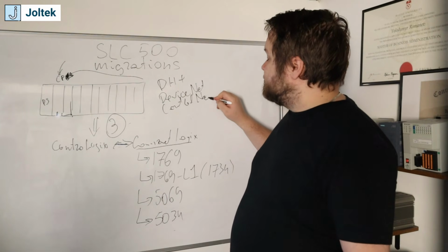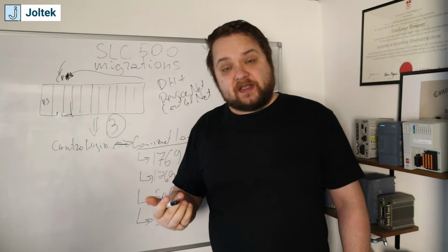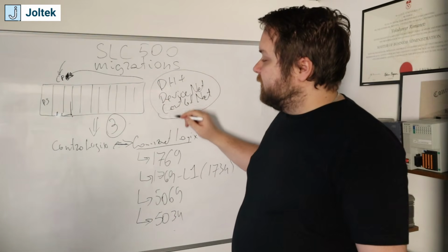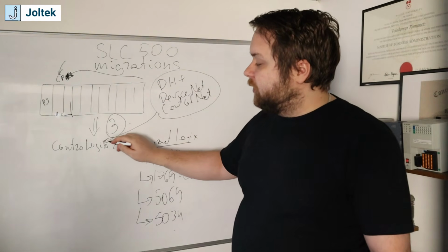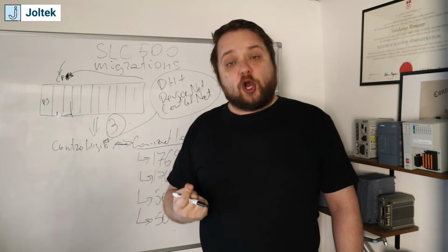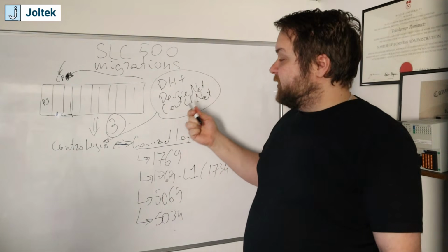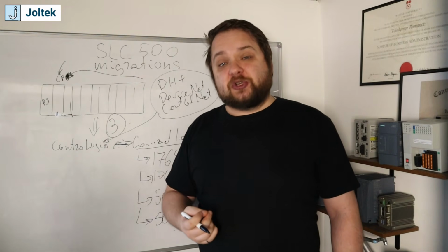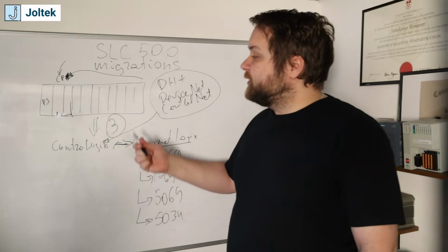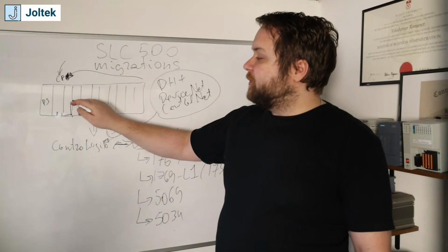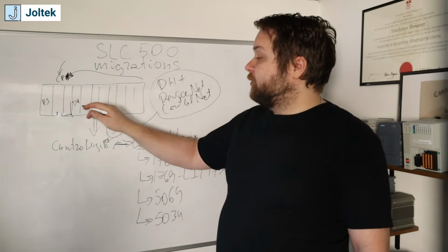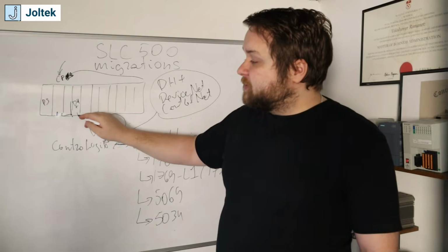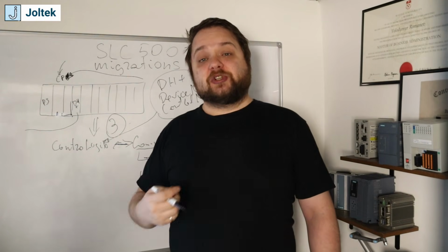And so, of course, depending on your plant environment, the only option for some of these protocols is going to be on the ControlLogix side. Now, I would argue that you should be eliminating these protocols and moving to EtherNet/IP as part of this migration, but it may be very costly. So it is common to see, for example, a Data Highway or again, ControlNet or DeviceNet card inside of these SLC 500 chassis that then talks to multiple points of I/O.